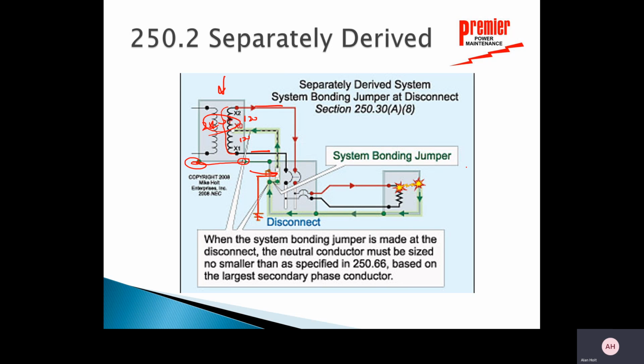Now, if I look down here at the load, there's my load. Again, there's my system bonding jumper right there, the little connection from the neutral to ground. But if I look at my load, there is no connection in my load. There's hot one side, hot the other side, 240 volts. There's no path to ground from the load, okay? Now, there is a neutral here, or not a neutral. There is a ground connection here. The case of all electrical cabinets are tied to ground, but there's no path for current, neutral current, to flow back.